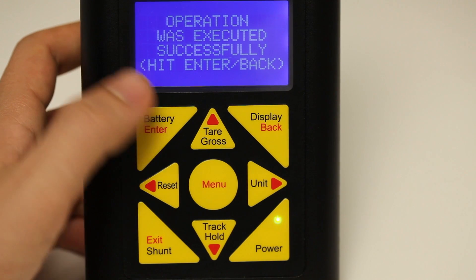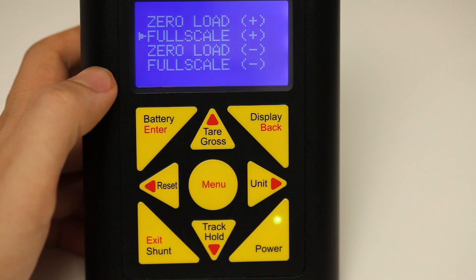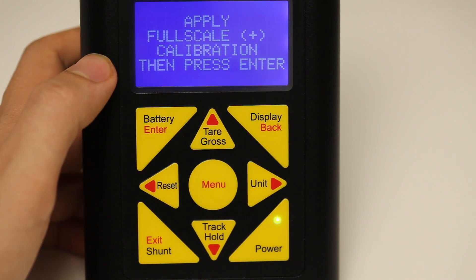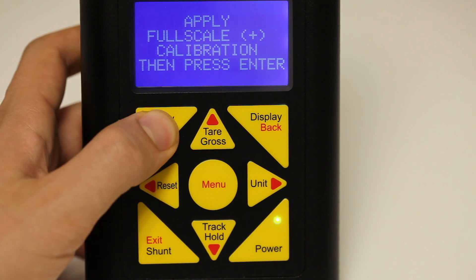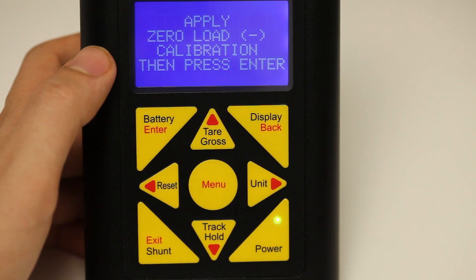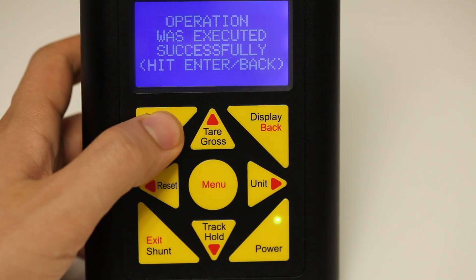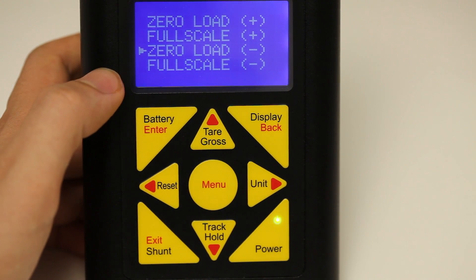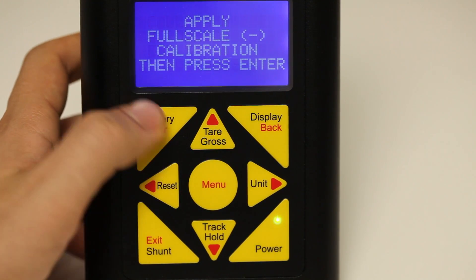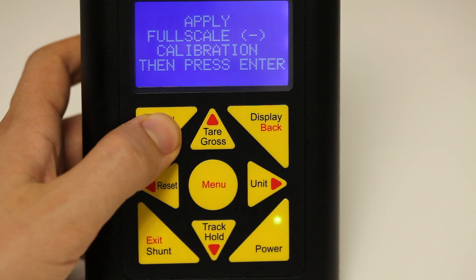Press enter again to acknowledge this operation was successful. Press the red down arrow key to select full scale positive. Apply a full load in the positive direction on your load cell and press enter to capture the reading from the load cell for the positive direction. Go into the zero load negative. With zero load on the load cell, press enter to capture the reading from the load cell. Press enter again. Press the down red arrow key to highlight full scale negative. With a full load in the negative direction on your load cell, capture the reading from the load cell.